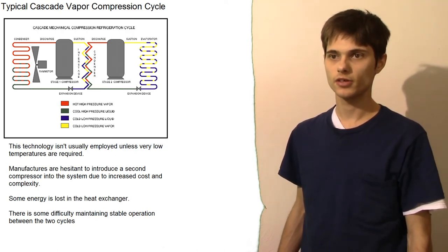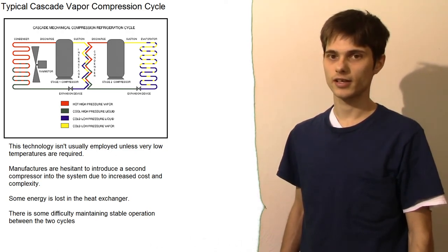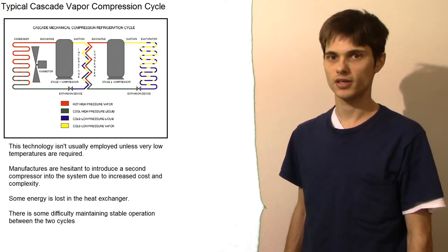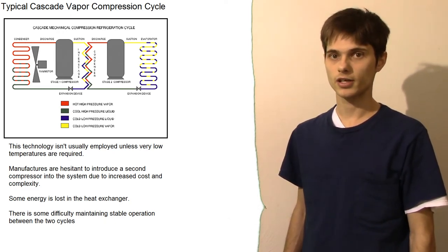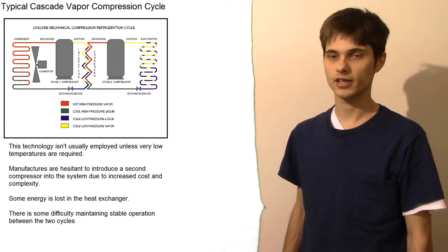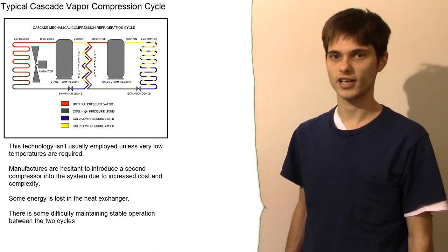So what I'm doing here, it doesn't have a good likelihood of working. The compressors really aren't designed to work with intermediate pressures on their suction side. That may cause a problem. And because we're actually moving more heat, we have to deal with the first law of thermodynamics.